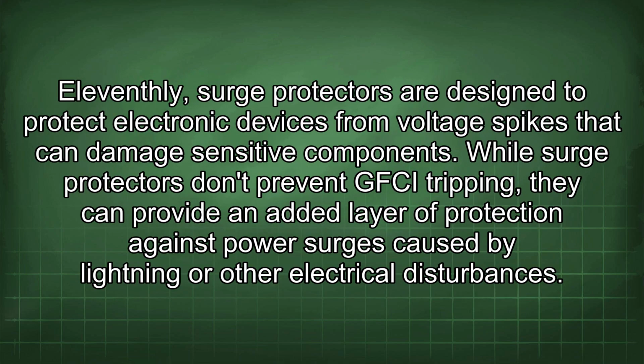11. Surge protectors are designed to protect electronic devices from voltage spikes that can damage sensitive components. While surge protectors don't prevent GFCI tripping, they can provide an added layer of protection against power surges caused by lightning or other electrical disturbances.